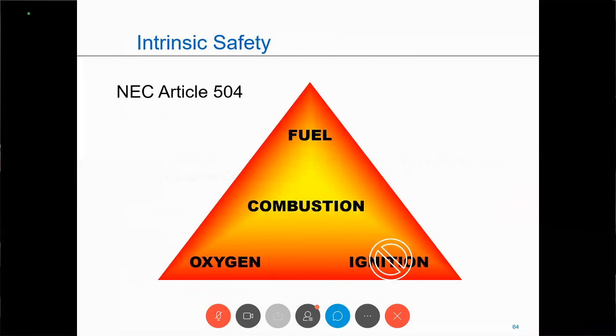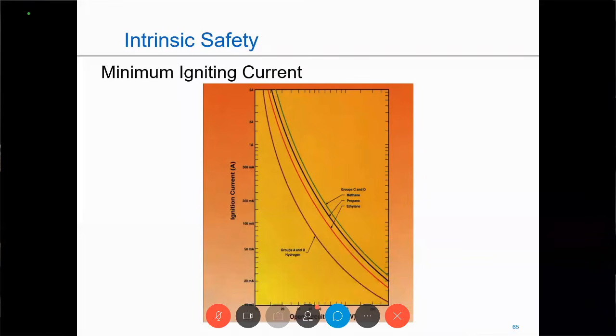And when it comes to intrinsically safe, here I'm effectively removing the ignition leg of my combustion triangle. This is going to be typically instrumentation, things such as 4 to 20 milliamp, 24 volts. And when I have current and voltage that are that low, where they intersect falls below the ignition curves of the particular gas groups. But what I have to prevent against is some kind of fault that could introduce more energy, and then that energy exceeds the ignition curves, which means it could be ignited.